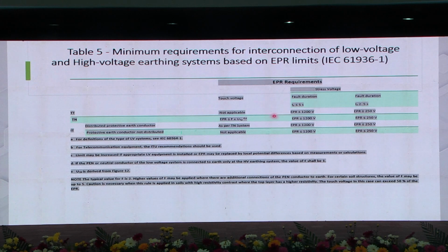Here, number one, this is the table as per IEC 61936, part 1. Here, we have to contain the EPR requirement. For the EPR requirement, for example, if it is a TT system, as already shown in the previous slide, you will not be subjected to the touch voltage. So you are safe. But the equipment voltage will be high, and depending upon the duration of tripping of the device, it will vary. Less than 5 seconds, it can be permissible up to 1200 volt, and beyond 5 seconds, you are permitted to have 250 volt.